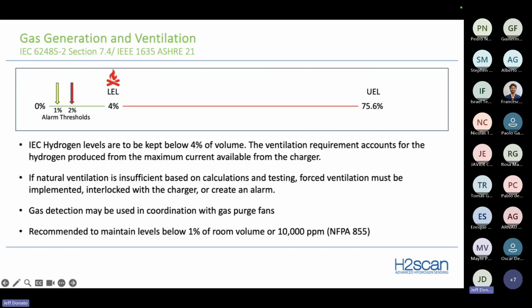So there's a vast range where this is explosive, and because of this vast range, we typically set alarm thresholds way down here in the 1% and 2% range. Most of the hydrogen sensors that you see have a cautionary alarm at 1% and then a critical alarm at 2%. So the goal is that we don't want to get anywhere near this 4% range.